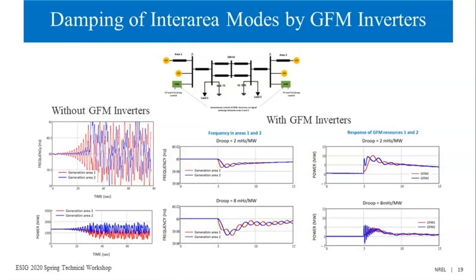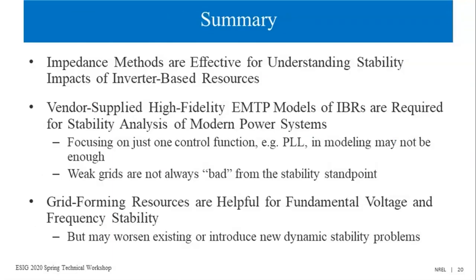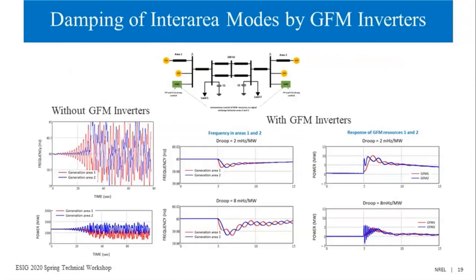This slide basically shows that grid forming inverters are good at damping interarea oscillations without any special controls. What it is showing is that when we talk about grid forming resources, we are modifying inverters around the fundamental frequency. So they will help us maintain fundamental frequency and voltage, and also damp oscillations around the fundamental frequency, but they may have issues away from the fundamental frequency, and that we need to address.